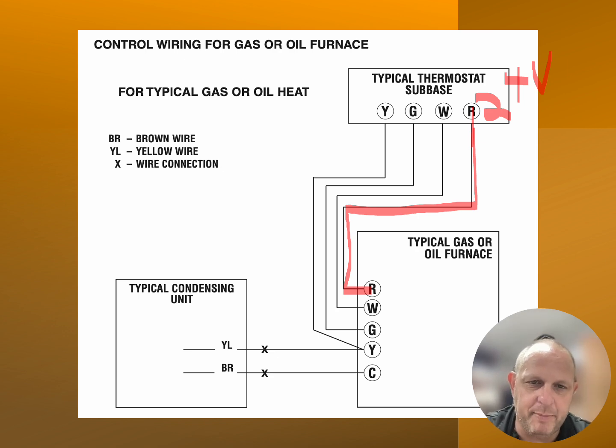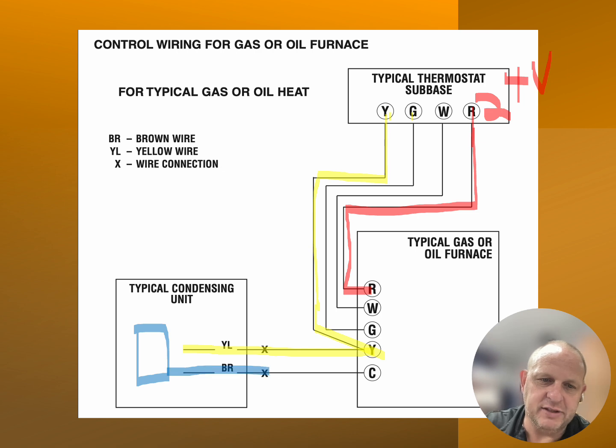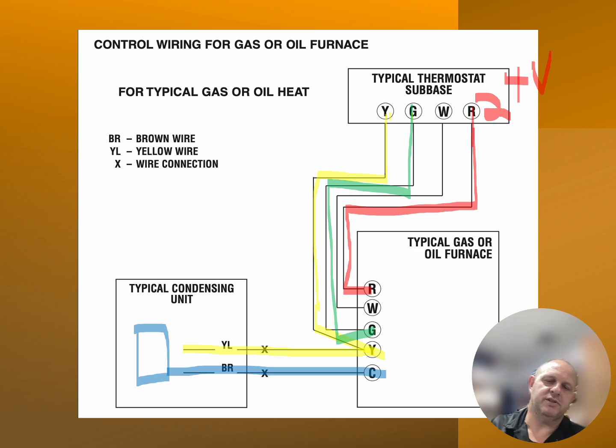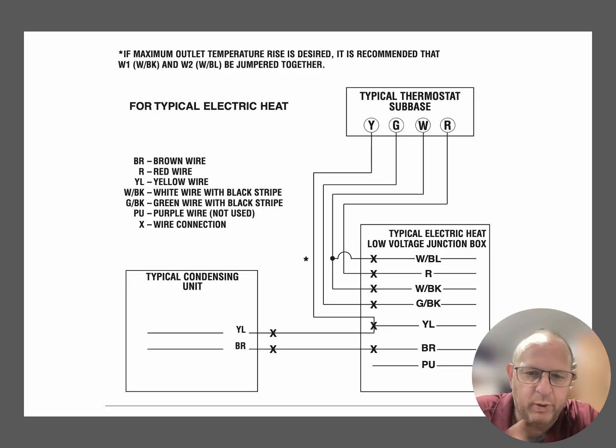Y terminal is going to come into the indoor unit, typically into a furnace control board. Once the furnace control board sees the Y terminal, that it gets a 24-volt signal, it will kick on the fan more than likely. We are also going to jumper in parallel out to the outdoor unit, just like that. And then what happens is we'll power a contactor out here. Contactor will complete the circuit back to the common on the indoor unit. So 2 wires to the outdoor unit on a single stage air conditioner. Some thermostats will send power out through the G terminal, okay? And that power will run back to the board, and then the board will kick on the fan. The W terminal is not used for the air conditioning, as that is heat only. Okay, so what we have here is your basic air conditioner with an air handler or electric strip heat.